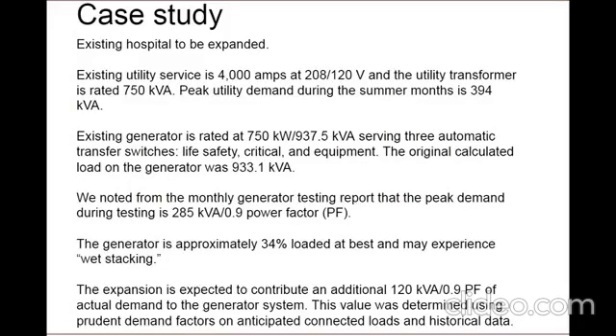Okay, there we go. Here we're looking at an actual project I was involved in recently. The project involves expansion of a 130-bed acute care facility, adding 5 operating rooms and an additional 15 beds for prep and recovery. The existing facility utility service is 4,000 amps at 208/120 volts. The service transformer is rated 750 kVA, and the current peak demand in the summer months is 394 kVA based on utility bills. The original designers of the existing building included a 750 kW generator. The connected load calculations indicate 933 kVA.